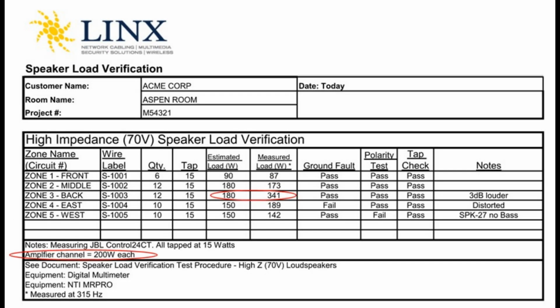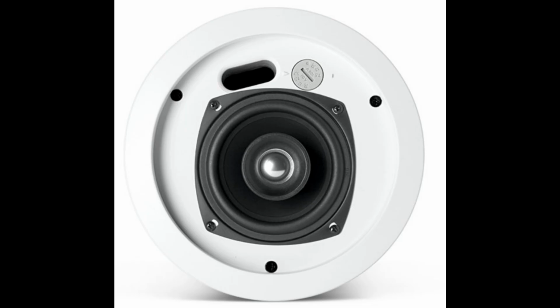The Zone 3 measured value has a problem. The measured value is approximately double the expected value, so I will assume the installer tapped the speakers at 30 watts instead of 15 watts.